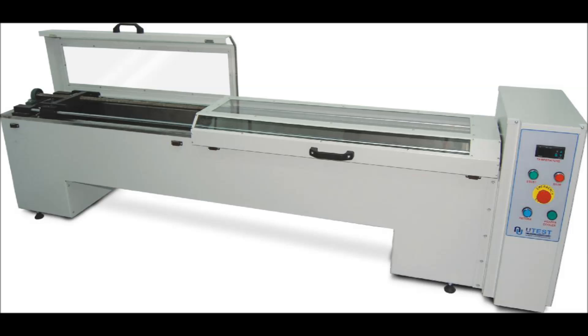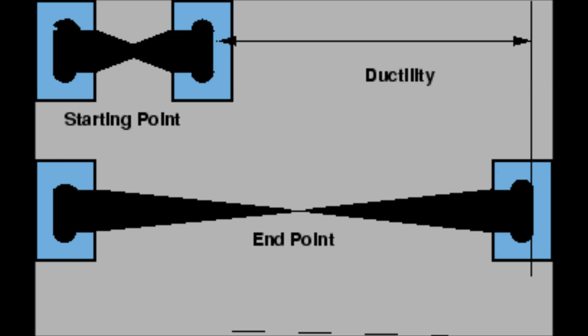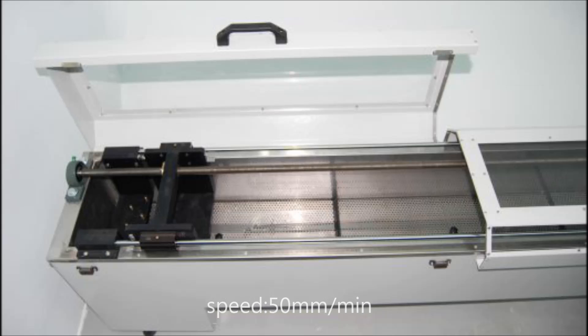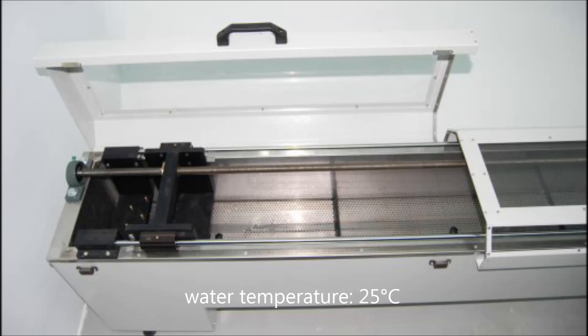UTEST UTAS-0400 ductility testing machine and UTAS-0420 ductility testing machine with cooling unit is used to determine the ductility of bituminous materials in a briquette mold by measuring the breaking elongation at a constant speed of 50 mm per minute in 25 Celsius water.